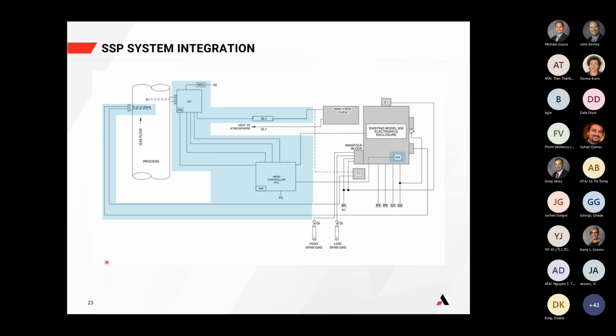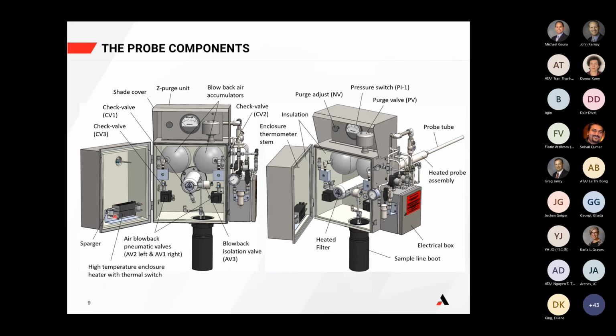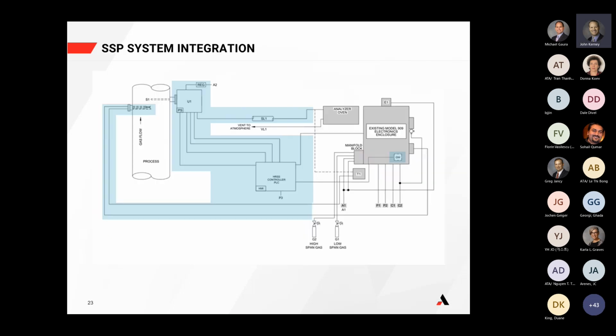And then if we go back to this photo here, you can see that there's a fin heater that controls the temperature of the enclosure, as well as a little air bath or sparger device to circulate the air within the enclosure to maintain constant temperature. So there's a heater within the actual filter element, a heater within the heated probe assembly, and then a third heater for the actual enclosure. Sorry, does that answer all the questions, or was there another? No, I think that covered them. If not, the folks can put in the chat and I'll continue to ask.